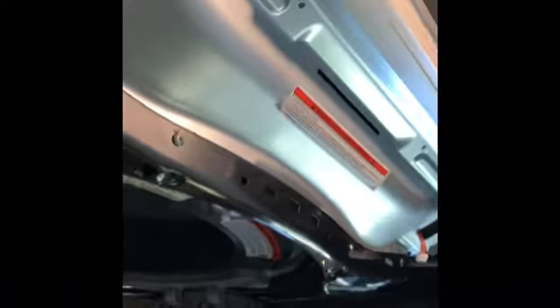Now a quick way to check if we're getting power to our display is check our low voltage. We know we're getting high voltage, so how do we check our low voltage? Go to this connector, and I already traced it from here all the way to there. So from pin, we're counting these pins from right to left: pin 1, 2, 3, 4, 5, etc. I believe that's how it's called out on the schematic. I'll post a screenshot. So we are looking for 13 volts DC.